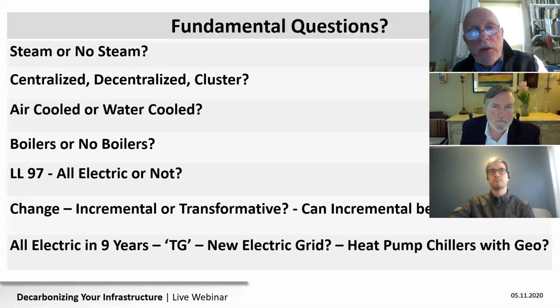Some fundamental questions came up during this process, as mentioned before: steam or no steam? Centralized, decentralized, or cluster? Air-cooled or water-cooled? These are fundamental questions you need to look at. If you're looking at variable refrigerant flow (VRF) versus a heat pump or a boiler, you can go from COPs of like 0.8 up to 4, 5, or 7 — so this makes a big difference. Boilers or no boilers — Local Law 97 is an electrification law, but can you get there?